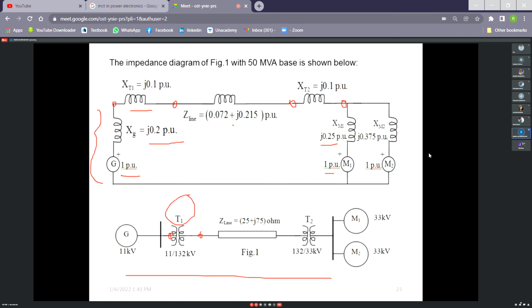As for the transmission line here, we have represented it only by series impedance. Why? A 132 kV transmission line means a medium transmission line, maybe long also. Why not the shunt part? Because here we assume that the system is healthy and steady, then the series current is far higher than the shunt current. That's why we have neglected the shunt branch. These things are not written in the book.